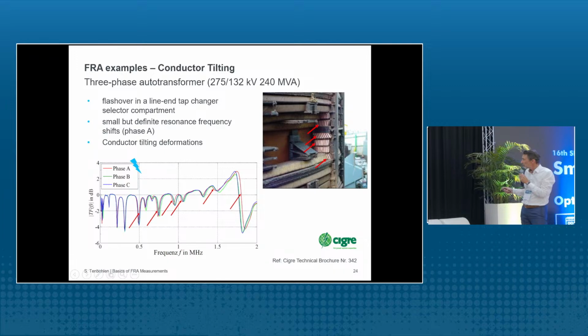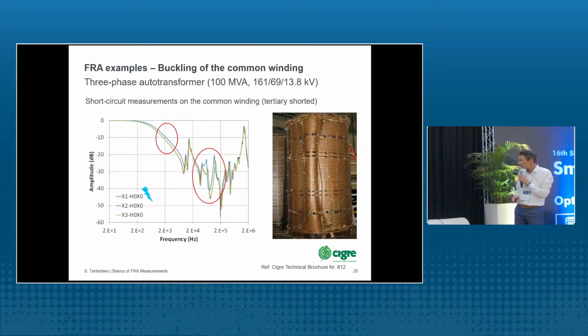Here, conductor tilting. You can see here the conductor is not vertical, but it's a little bit shifted due to axial forces. This is the frequency response. Red phase A shows significant differences from B and C, everywhere here where the red arrow is, and therefore you can see this transformer is not okay. And because of this FRA, this transformer was scrapped. Here we have buckling, a picture of the buckled transformer. Here again the FRA, and you can see the green and red phase are really on top of each other. So we have here a phase-based comparison, but the blue one is really different, which shows we have a problem in the blue phase.